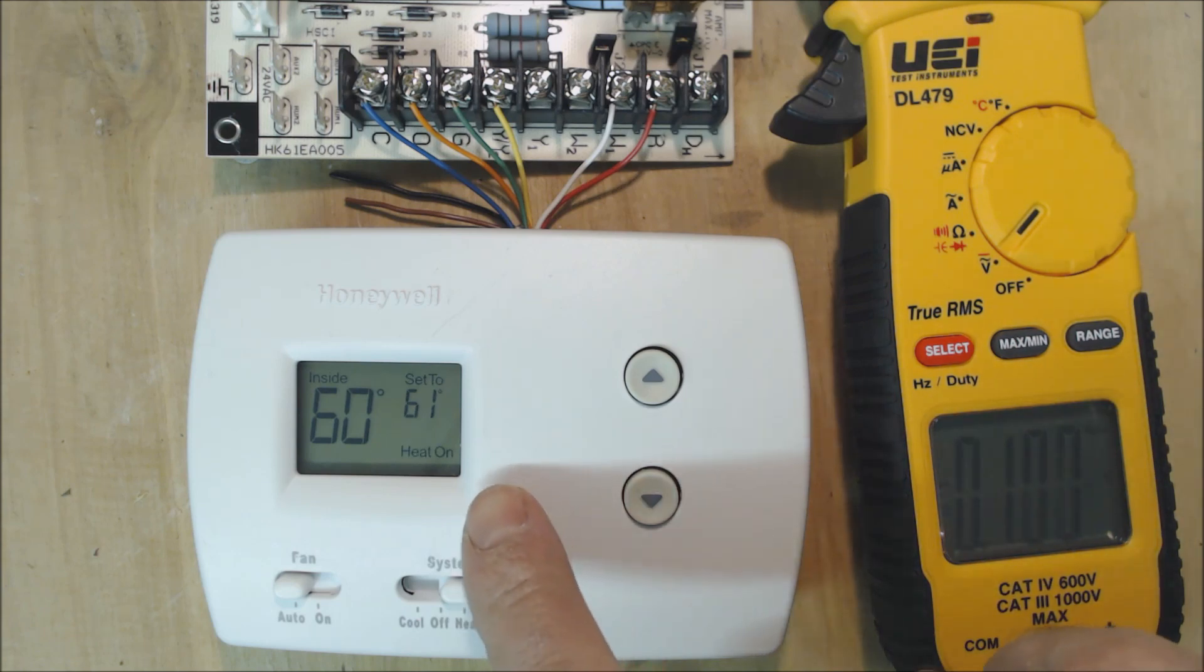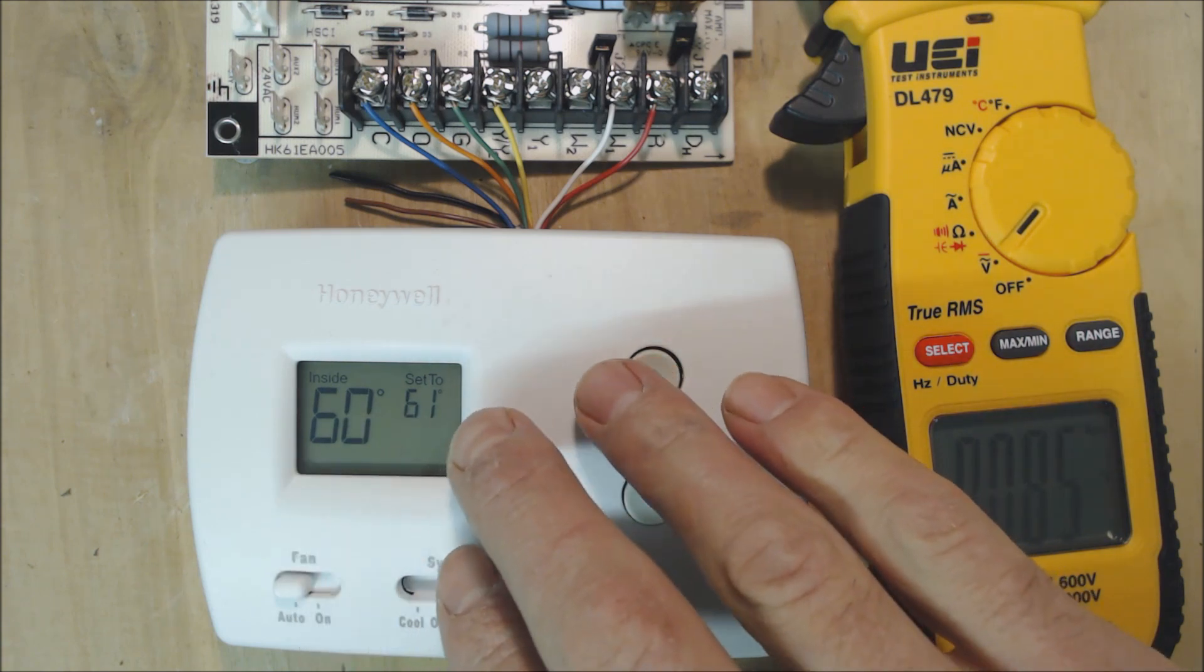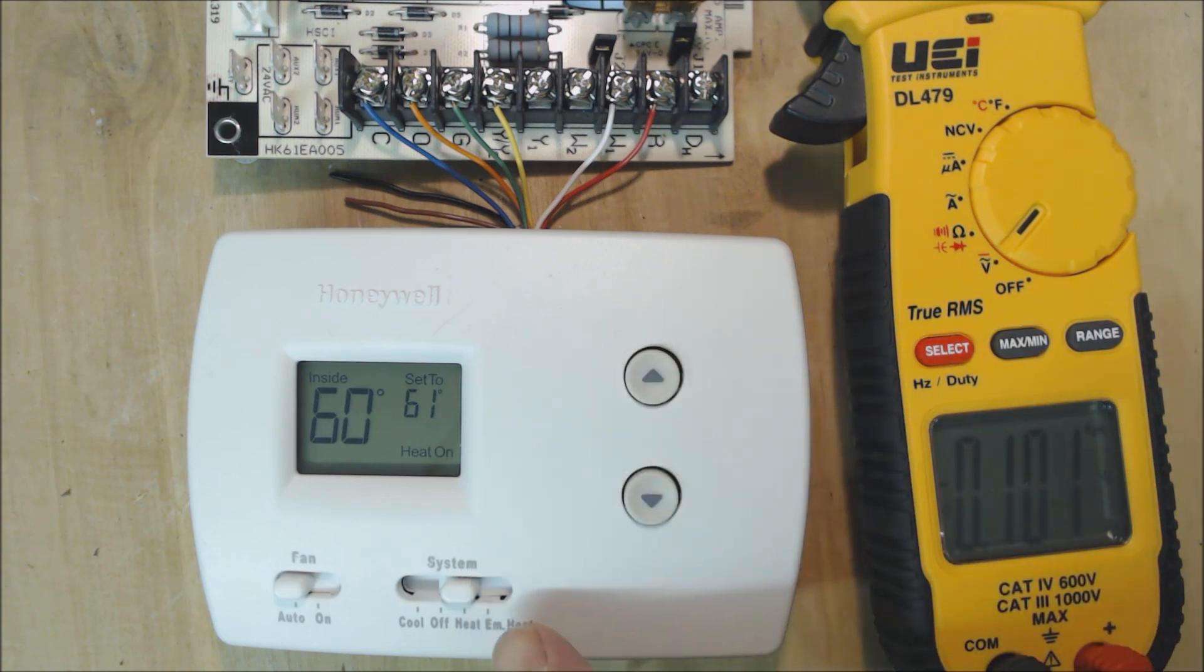If this thermostat is only calling for one degree above what it is in the room, this thermostat is going to run the heat pump only. It's not going to run the auxiliary heat, and it's definitely not going to run emergency heat because you don't have it set on emergency heat right now.